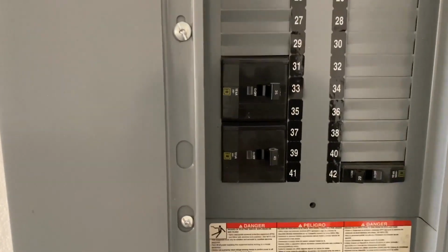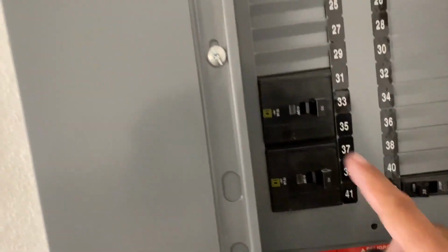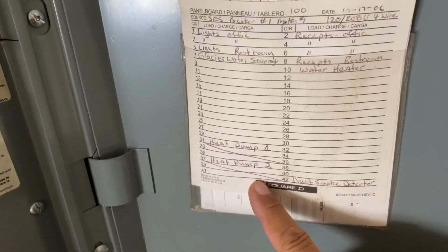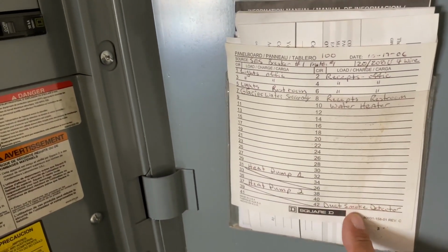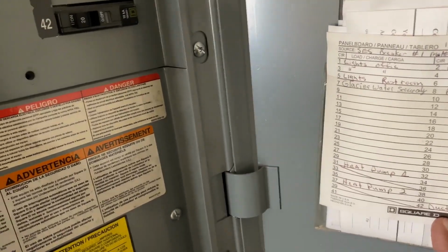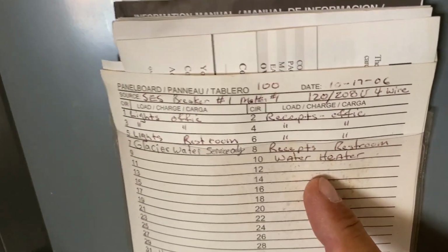So your architect should actually be looking at these things, or his engineer. I look at them on behalf of the engineer. Plus, I want to know what's happening out here. We have 2 large breakers, which, as it does show, are for our rooftop HVAC units that we just looked at. There's a duct detector that goes to one or both of the units, and those are here on this breaker. And then we have another large breaker, a 35. Fortunately, it tells us. Sometimes if you're lucky, if they make changes, they'll put a marker here to tell you. In this case, there have not really been changes made since this original schedule.